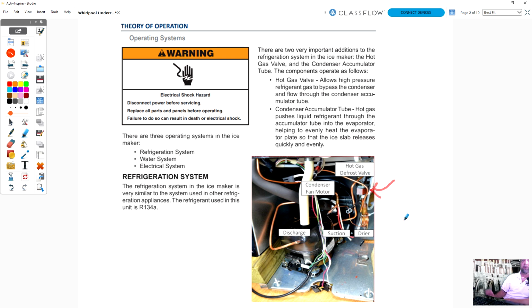If you're not familiar with how these ice makers work, the refrigeration system is just like a refrigerator. It has a condenser and evaporator, but it doesn't have a defrost system like a refrigerator. It uses high pressure refrigerant straight from the discharge line. Normally this would go into your condenser, but when it wants to drop the ice, this hot gas valve opens up, and that freon doesn't go to the condenser. It goes straight from the compressor to the evaporator, and that's how the ice slides off the unit.